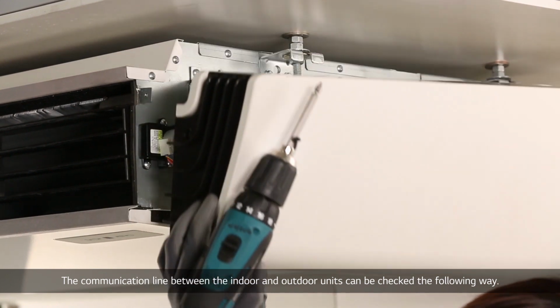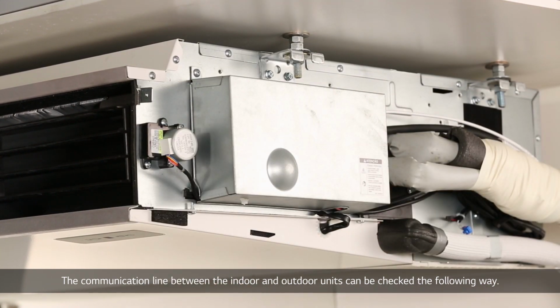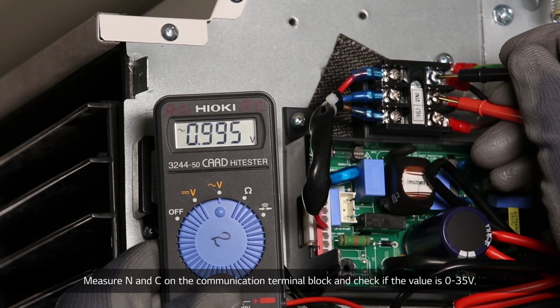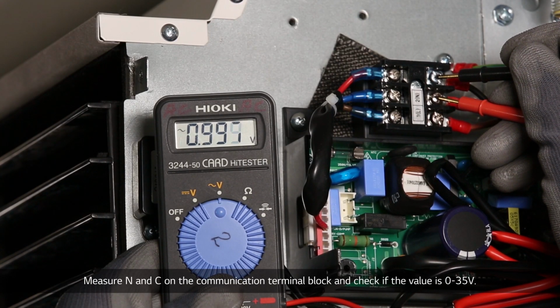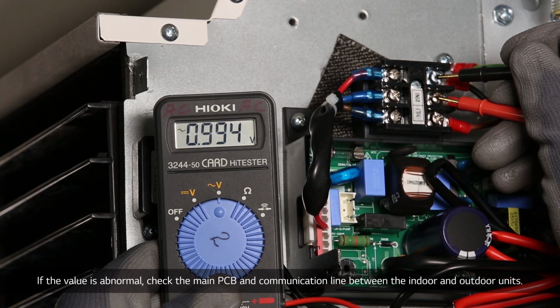The communication line between the indoor and outdoor units can be checked the following way. First, separate the indoor unit side panel, and then remove the control box cover. Measure N and C on the communication terminal block, and check if the value is 0 to 35 volts. If the value is abnormal, check the main PCB and communication line between the indoor and outdoor units.